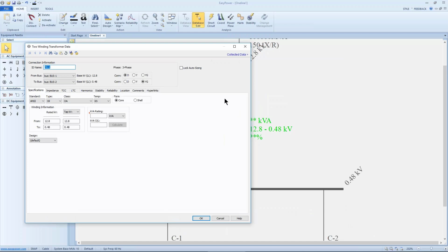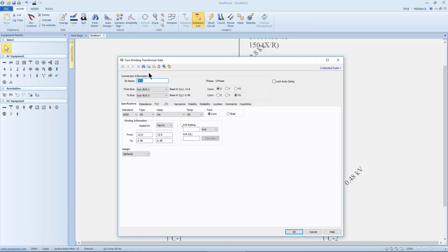Double click on the transformer. Now all this information comes from the nameplate. He said, "Jim, I've looked at the transformer nameplate. It's an oil-filled class OA, works with a fixed 65-degree rise. It's a delta Y with the Y grounded, and it's a 1000 kVA." So I type in 1000.